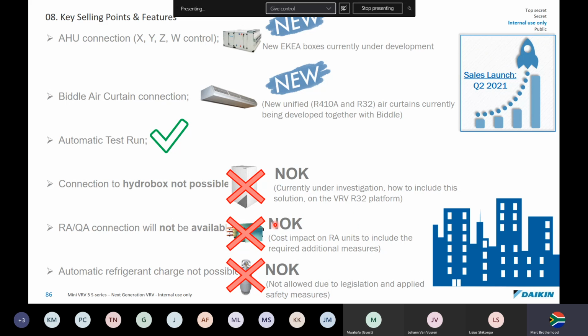But for now, there are cost impacts on RA units to include the required additional measures. They're going to have to include leak detection on the current Amura range, and they're saying it might be a bit too expensive for now. And for now, there's no automatic refrigerant charge possible. Why? Because of the legislation. If you use R32, you have to calculate the charge according to your pipe run, so your installation has to be accurate. Legislation does not allow automatic refrigerant charging of a VRV system.